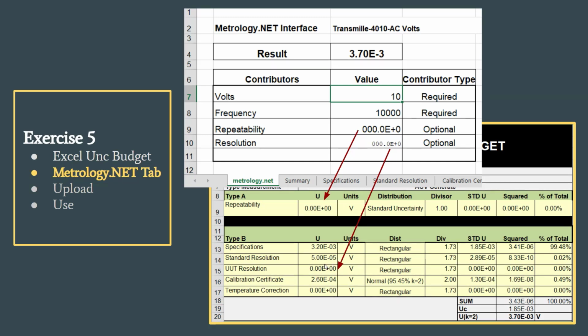And by default, when we build these, we build them with the minimum amount of measurement uncertainties, so that customers come in and do that. So by default, we put zeros in here. But if you guys have another number, you can put another number in there. And then if you have something that's doing some kind of base repeatability that you've done, or reproducibility, you can add that into these spreadsheets as well. We just don't have them in our examples.